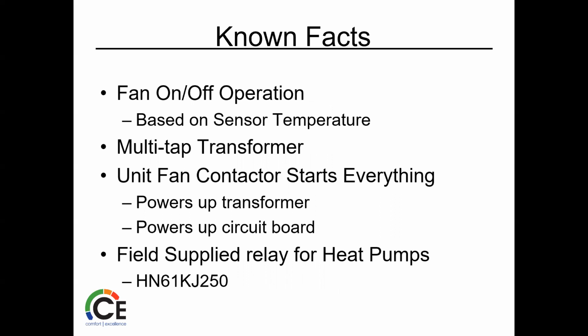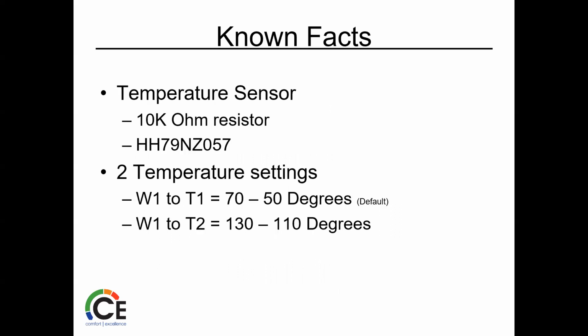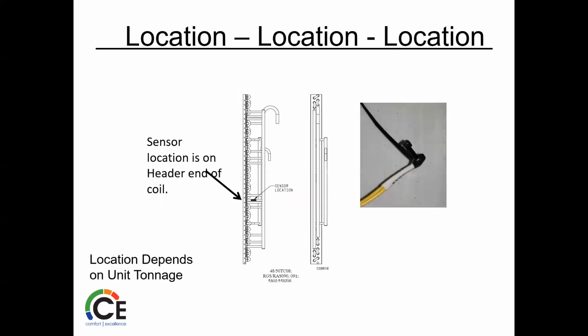Multi-tap transformer. Unit fan contactor starts everything, powers up the transformer, powers up the circuit board. Field supply, again, relay for heat pumps, just like the one. 10K ohm resistor. So again, if you've got that 10K chart, if you're testing that resistor, you can use that chart, you know what's going on. T1 is just the W1 connection. So 70 to 50 degrees, W1 to T2, 130 to 110 degrees. So that's what you're looking for when we want this operation.